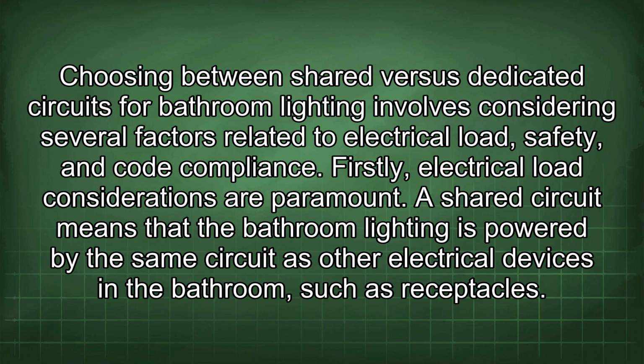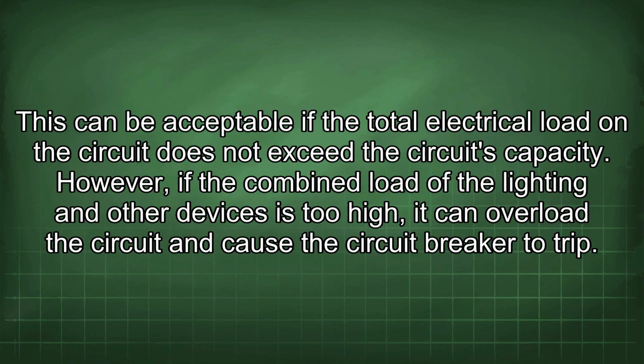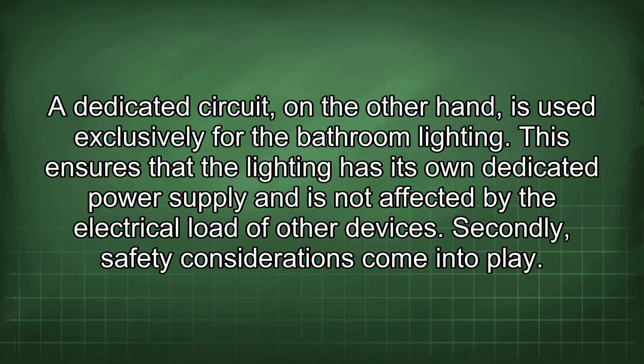and code compliance. Firstly, electrical load considerations are paramount. A shared circuit means that the bathroom lighting is powered by the same circuit as other electrical devices in the bathroom, such as receptacles. This can be acceptable if the total electrical load on the circuit does not exceed the circuit's capacity. However, if the combined load of the lighting and other devices is too high, it can overload the circuit and cause the circuit breaker to trip. A dedicated circuit, on the other hand, is used exclusively for the bathroom lighting.